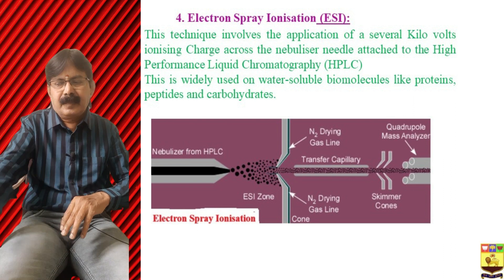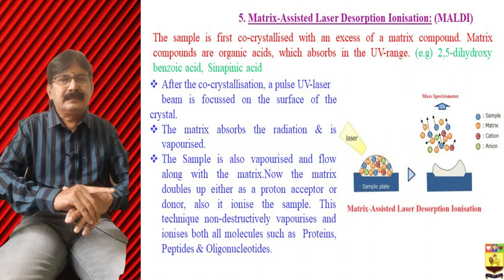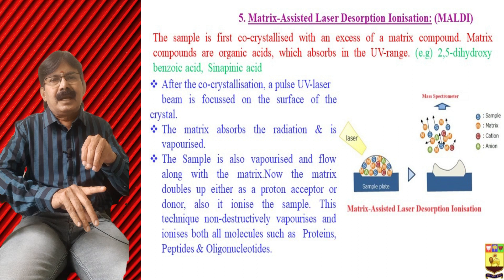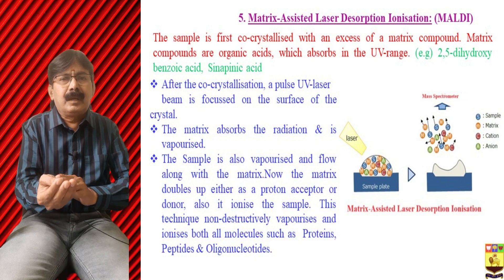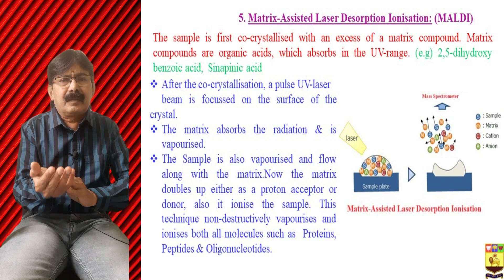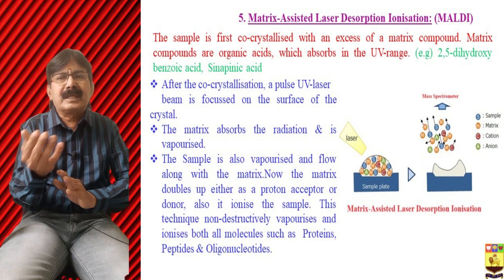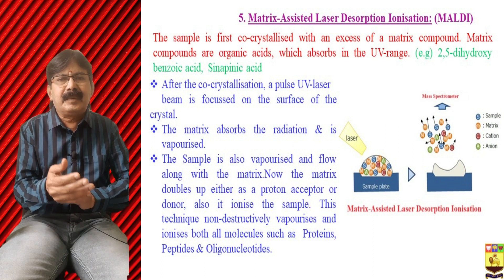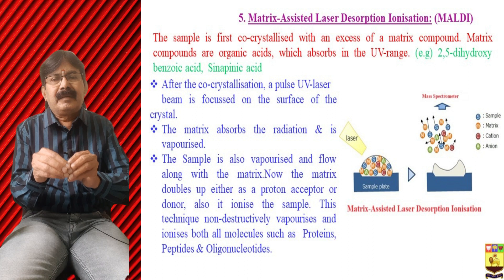The fifth and final technique is matrix-assisted laser desorption ionization (MALDI). First desorption takes place, then ionization. The first step is forming the matrix: the sample is co-crystallized with a matrix compound, generally 2,5-dihydroxybenzoic acid or sinapic acid, which is a derivative of cinnamic acid.